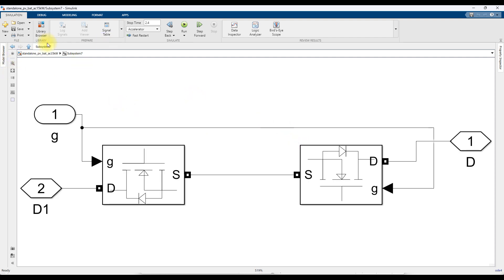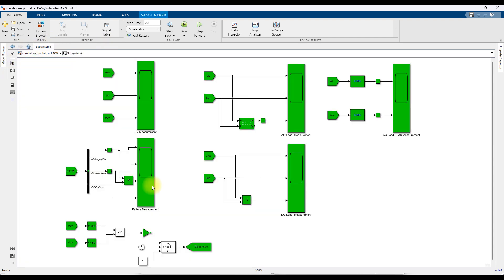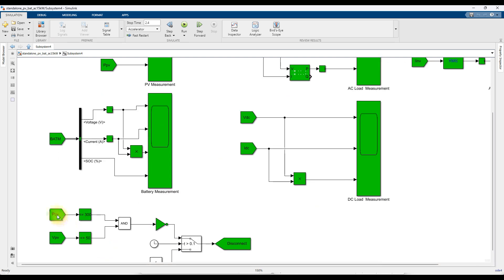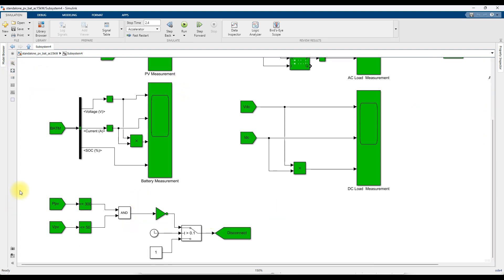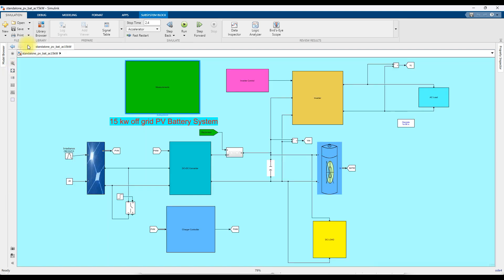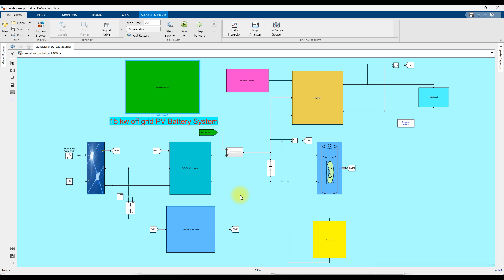Here we have a circuit breaker that operates based on two conditions: when the PV power is less than 300 watts and the PV voltage is less than 50 volts, the PV array system will be disconnected from the system; otherwise it will remain connected. Based on this control logic, the PV array is connected to the battery during daytime for charging and supplying the load.